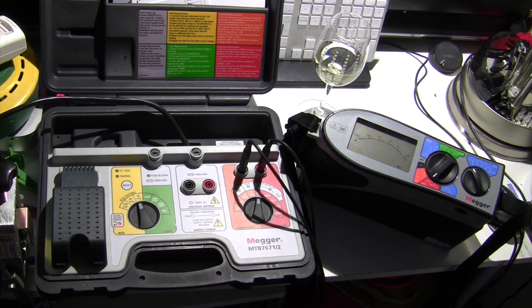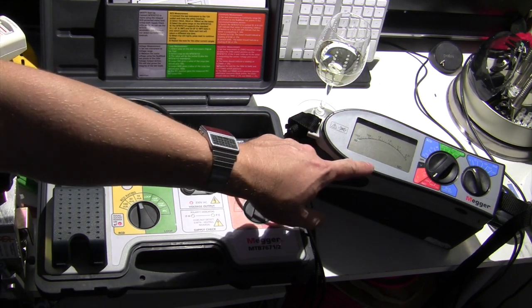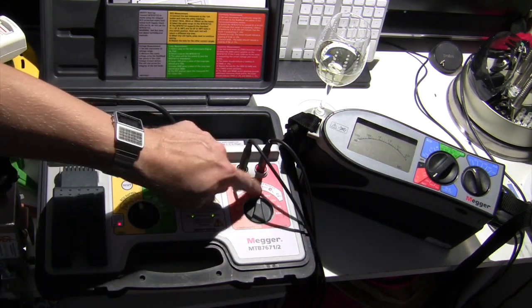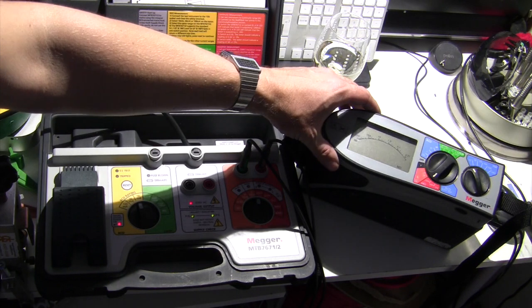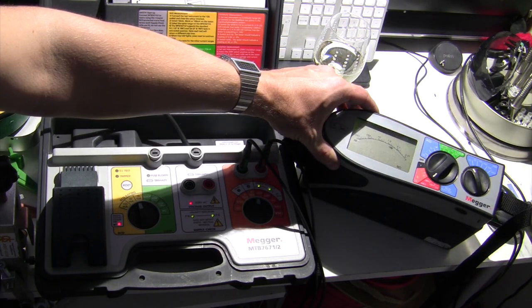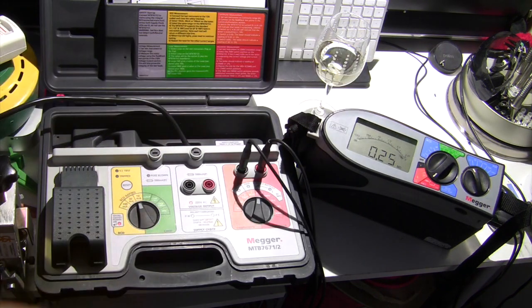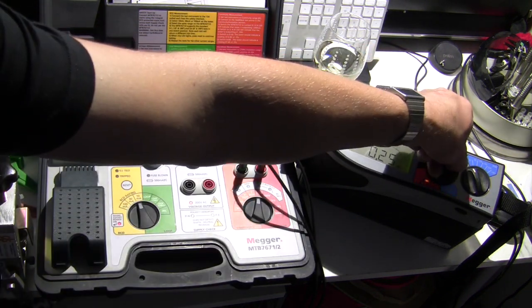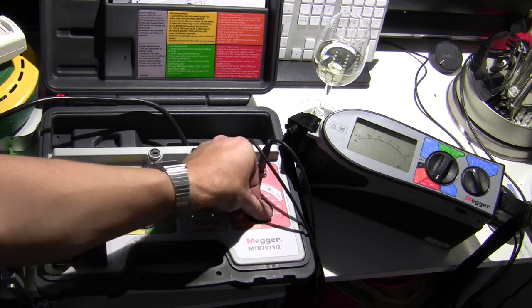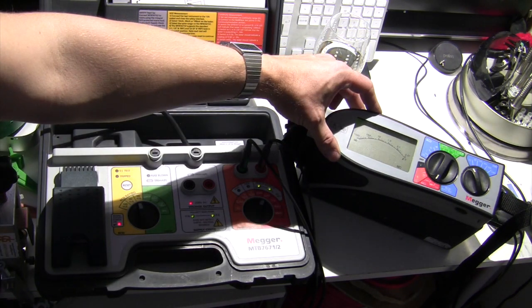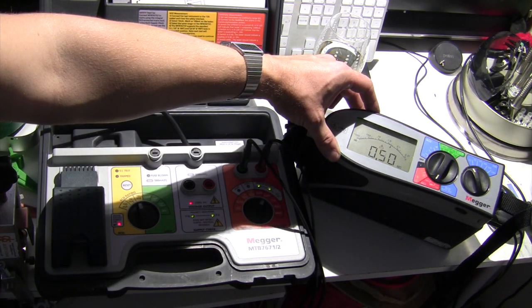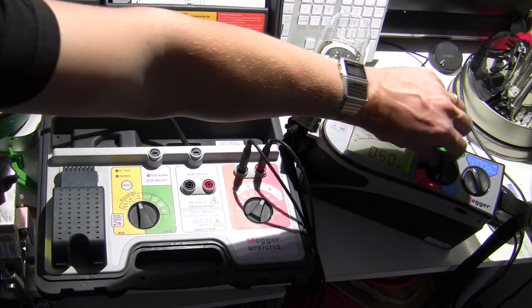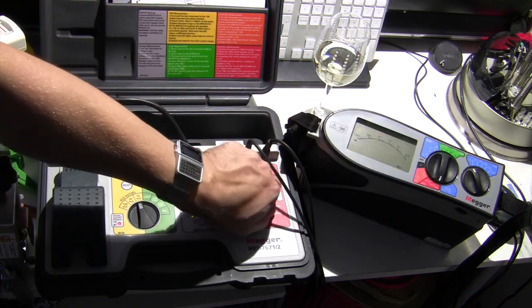So we're going to squirt 250 volts DC into here. If it's successful, we should get a 0.25 on the display, and the two green lights should light up to indicate that the voltage and the current expected from the tester are okay, and that is exactly what we have got. Switching it to 500 volts, we should get a 0.5 on the display, and again the two green lights, and we can also test it to a kilovolt.